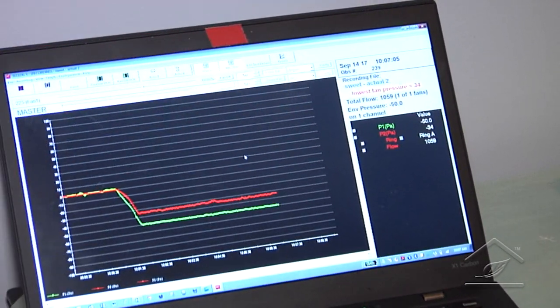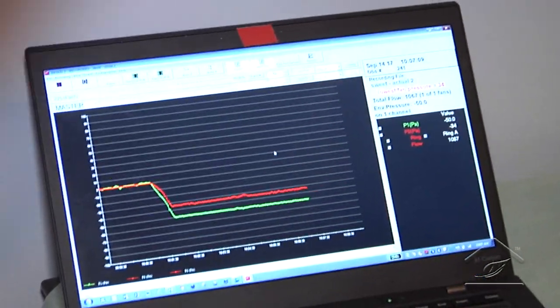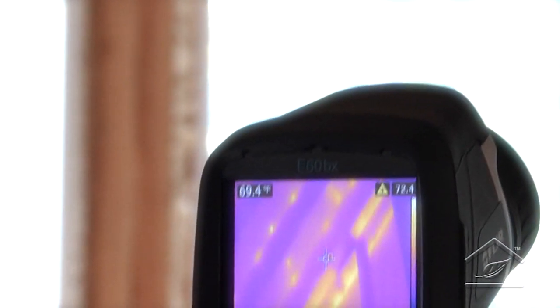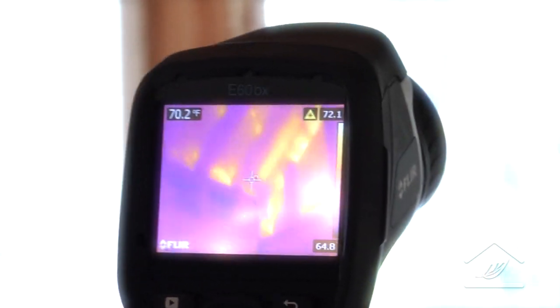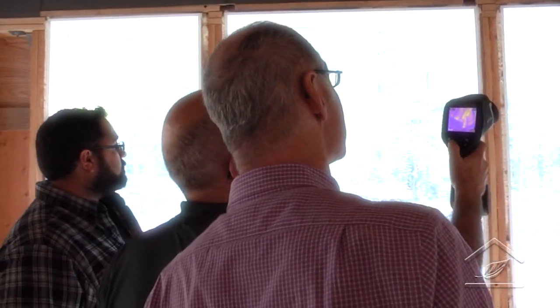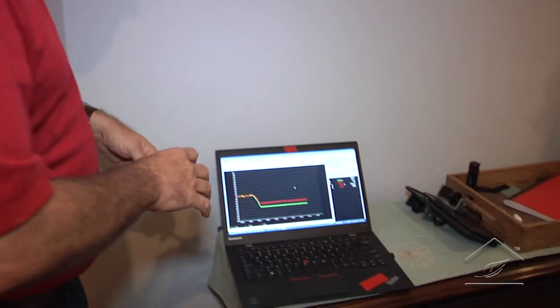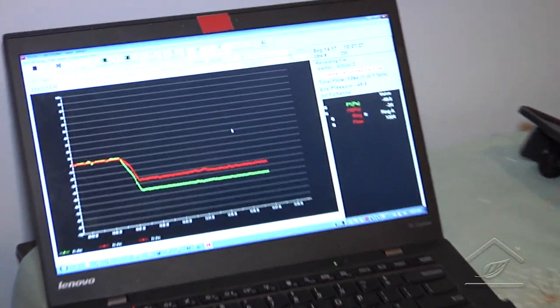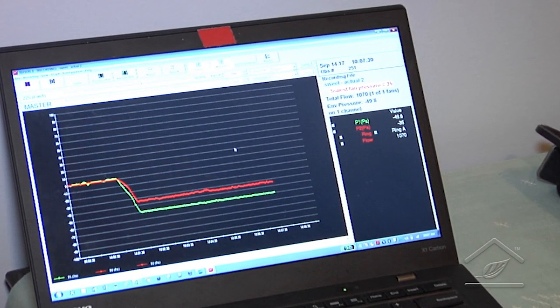You're at about 1,060 CFM — cubic feet per minute of air — and that's a great number to have in your house. It's less than half of what we had before when we did our previous test. Great job — you found all those leaks that you now sealed up. Overall, you need to be very proud about that number. This really is the sign of saving energy and sealing up a house with all this volume — such a small amount of cubic feet per minute.